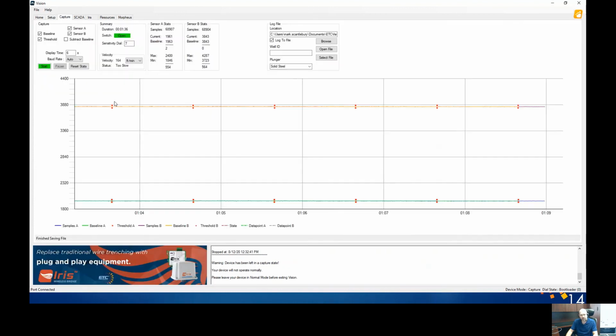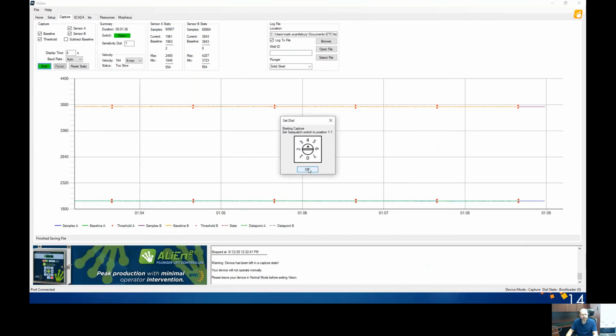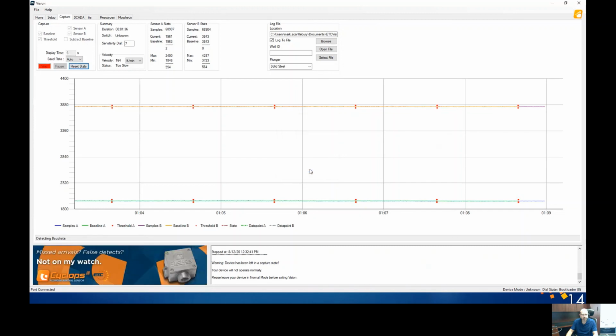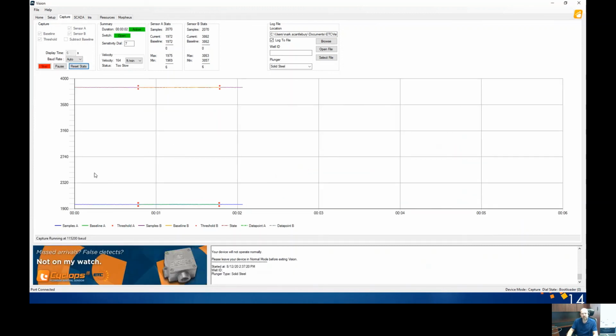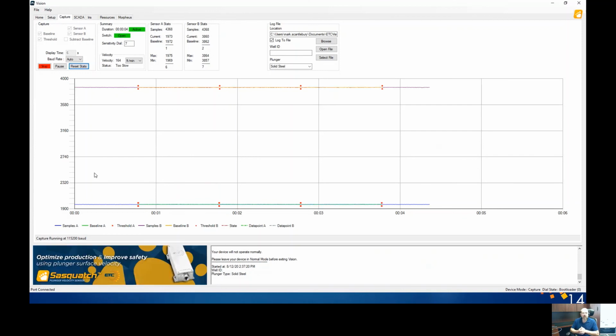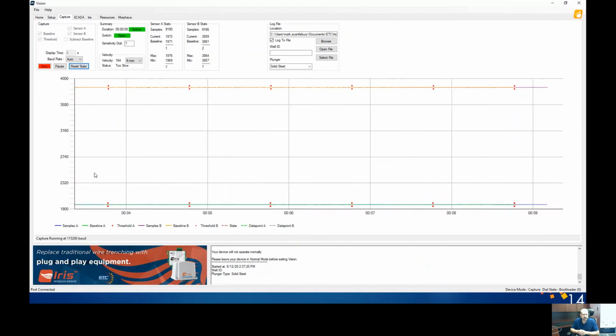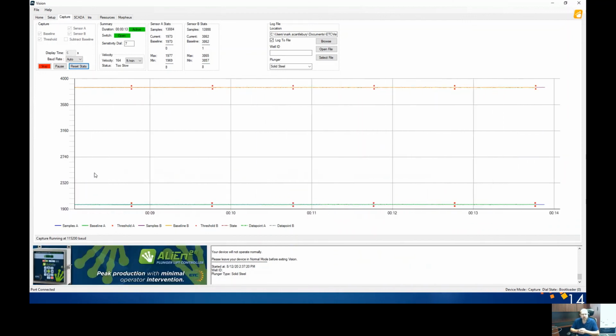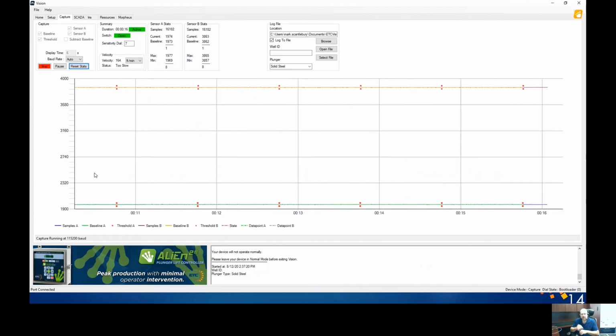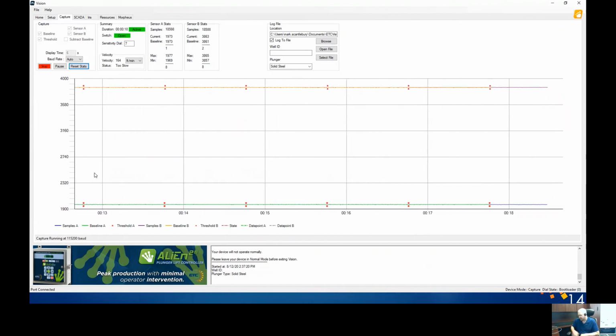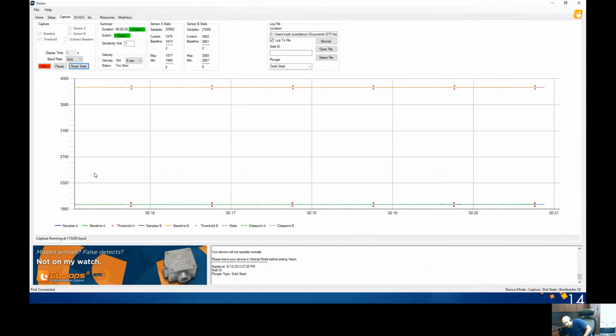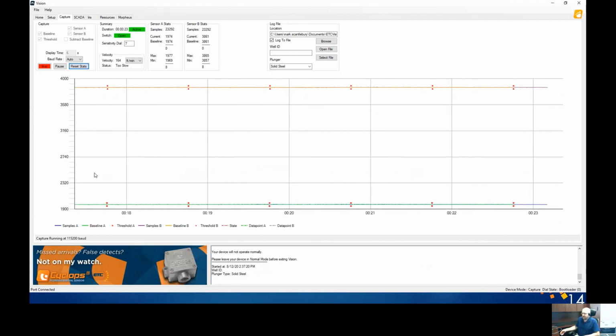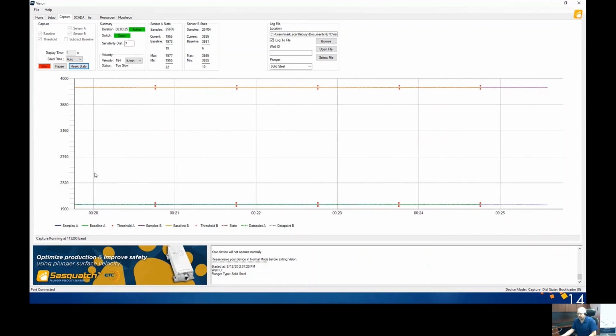We're going to go over to capture here, and we're going to start it. And once again, it wants you to be in an operational mode, so between 1 and 7. And when we start this, you can see with the Sasquatch, there are 2 waveforms happening here. We have the baseline and the samples are relatively the same because there is nothing affecting the Earth's magnetic field. You can see the threshold, we're on a sensitivity dial setting, so it's a really small change from those baselines. And it's sitting here looking for an arrival of the plunger. And so I'm going to take a screwdriver and run it underneath here.